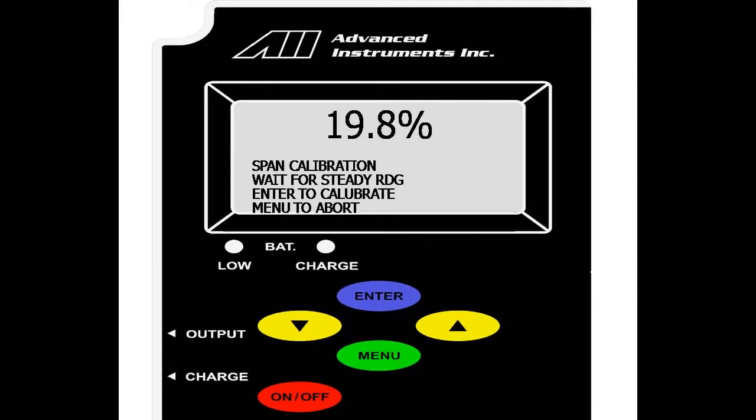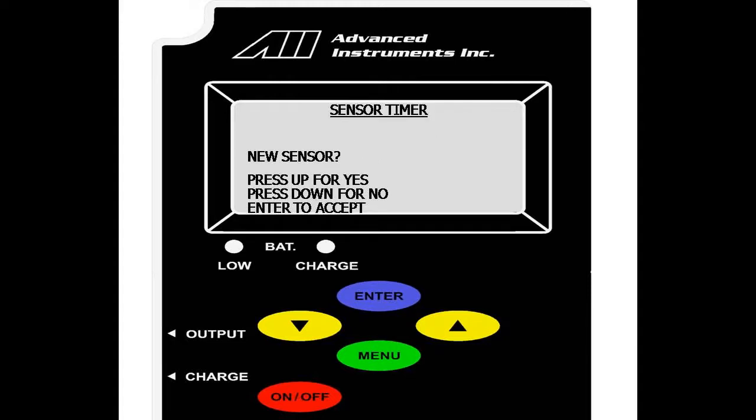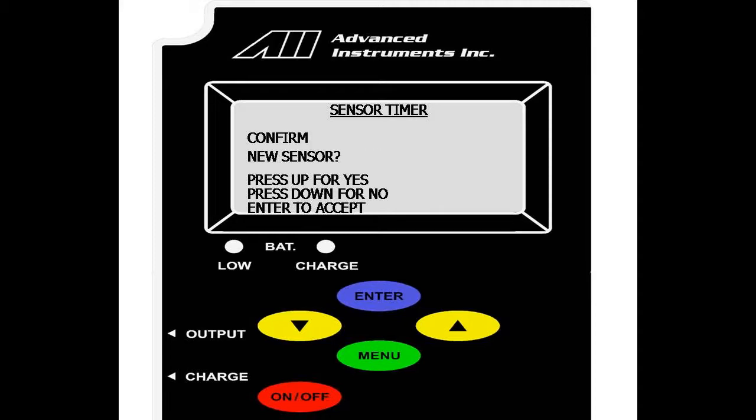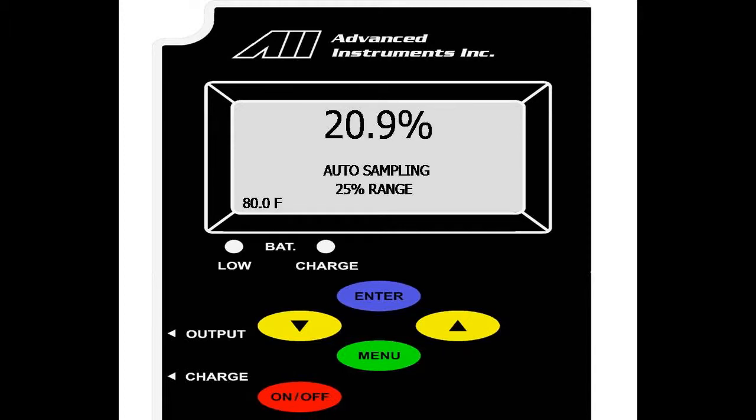Here, we have a live reading of the oxygen sensor and have the option to hit enter for calibration, menu to abort. This is to ensure that the reading is stable and not fluctuating. As you can see here, the reading is stable. We select enter. We are prompted if this is a new sensor. Up or down for no and yes. Since this is a new sensor, we will hit yes and we are prompted to confirm this selection. Again, yes. We are now seeing that calibration has passed. We will then be taken to the main menu and show the value of 20.9, the sensor in ambient air.